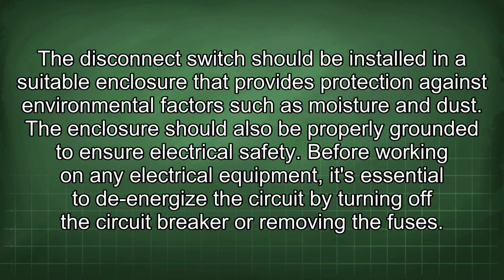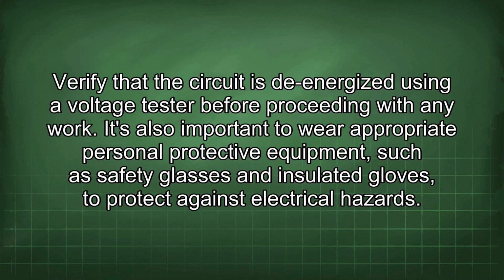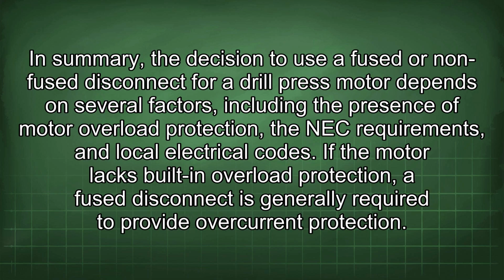Before working on any electrical equipment, it's essential to de-energize the circuit by turning off the circuit breaker or removing the fuses. Verify that the circuit is de-energized using a voltage tester before proceeding with any work. It's also important to wear appropriate personal protective equipment, such as safety glasses and insulated gloves, to protect against electrical hazards. In summary, the decision to use a fused or non-fused disconnect for a drill press motor depends on several factors, including the presence of motor overload protection, the NEC requirements, and local electrical codes.